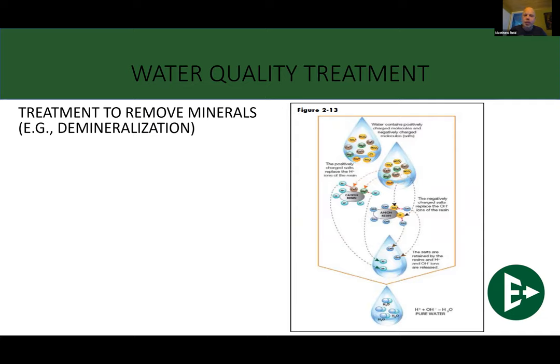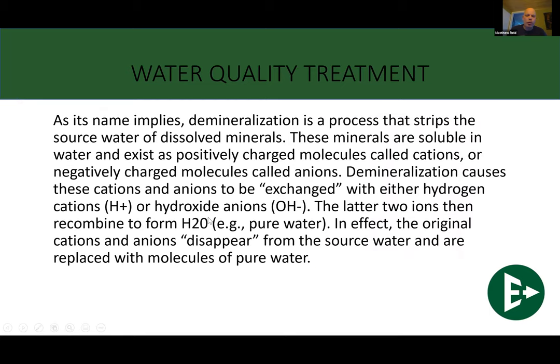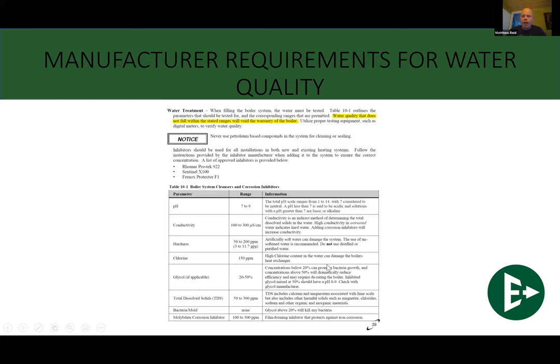But in this case, when we're talking about our ion exchange, we're only talking about changing it now with hydrogen and hydroxide ions, to create at the very end of it, once we do our ion exchange, pure dihydrogen monoxide, H2O, pure water. That's the closest we can possibly get to pure water by doing demineralization. When you remove these other salts and minerals from the water, you're leaving it with these guys. And that is essentially what we're looking for.